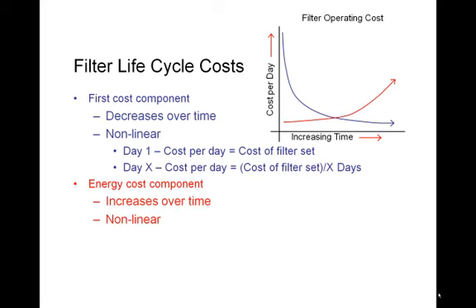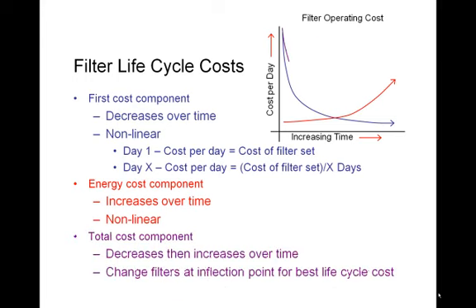Meanwhile, the energy cost tends to increase with time. As the filter loads up, the pressure drop increases, and you hit a point with most filters where it starts to break down and skyrocket, and the energy costs go up because the static pressure goes up. It goes back to that fan power equation I showed you earlier. And if you add those two curves up, you end up with a curve that has an inflection point, and it's at that inflection point when your best life cycle cost is achieved.